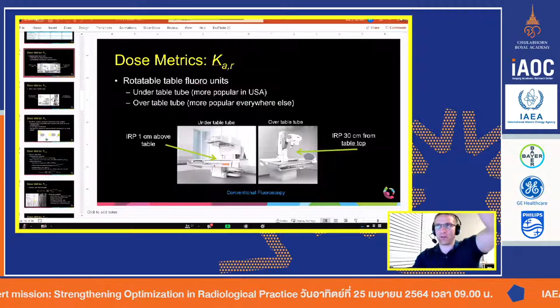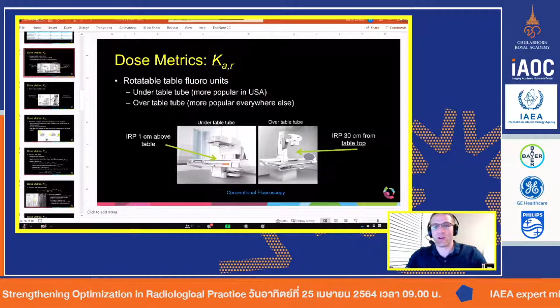So yes, the nice thing about these systems right here is that the tube can go really high. You can actually do radiographic imaging, normal DR, CR type imaging on these machines. So a big reason why these machines are used everywhere, mostly outside of the US, is because they're multi-purpose. You can do both fluoro, and then if you pull the tube up, you could actually do abdomen imaging or short field chest imaging. You can do long bone imaging for the legs and stuff because the system will move. So they're actually very versatile. You can actually do scolies on these machines. You can tilt the machine up, get the patient vertical, and the tube will just drop and you get a nice scolie shot. Whereas you can't do that with these.